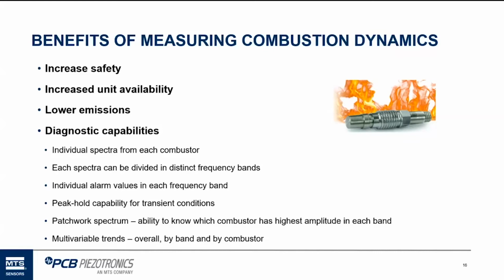Some systems have what's called a patchwork spectrum, where the system will let you know which combustor has the highest amplitude in each band, so you'll know if there could be a possibility that the fuel nozzle itself is not right in that one combustor. That's a possibility. There's other things as well that could be wrong. And then you can do different trends, multivariable trends, by band, by combustor, and this is a common monitoring parameter that plants do.